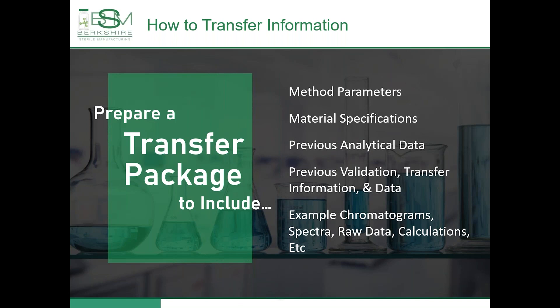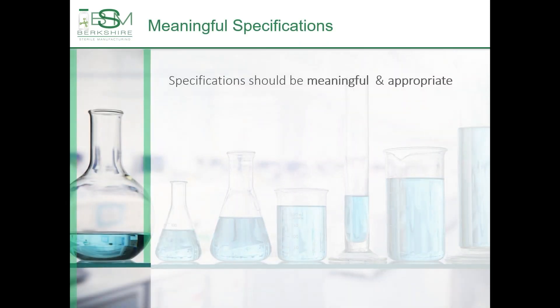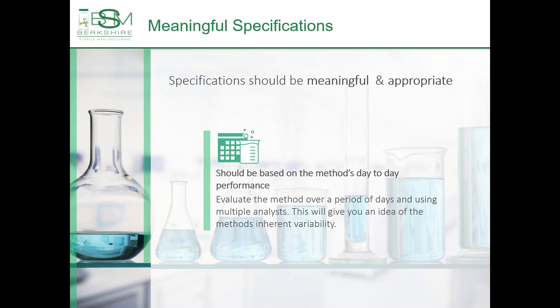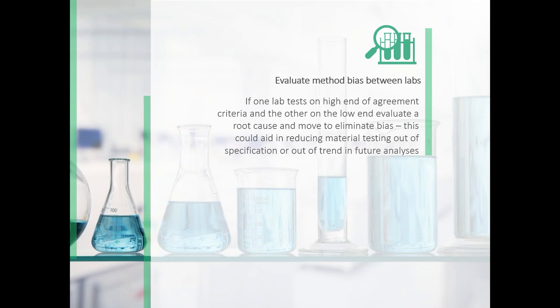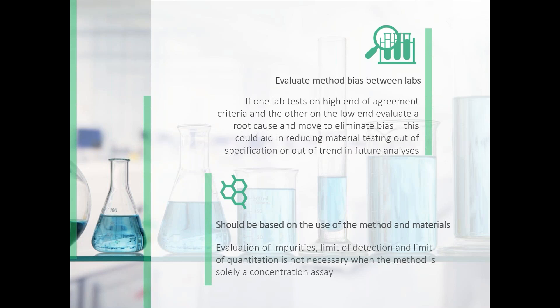Specifications submitted to the receiving lab should be meaningful and appropriate. The specifications should be based on a method's day-to-day performance — evaluation of the method over a period of days using multiple analysts will give you an idea of the method's inherent variability. An evaluation of any method bias between the receiving lab and the transferring lab should be done. If one lab tests on the high end of agreement criteria and the other on the low end, evaluate a root cause and move to eliminate any bias. This work ahead of time could aid in reducing material testing out of specification or out of trend in future analyses. Specifications should be based on the use of the method and the materials — for example, evaluation of impurities, limit of detection, and limit of quantitation is not necessary when the method is solely a concentration assay.